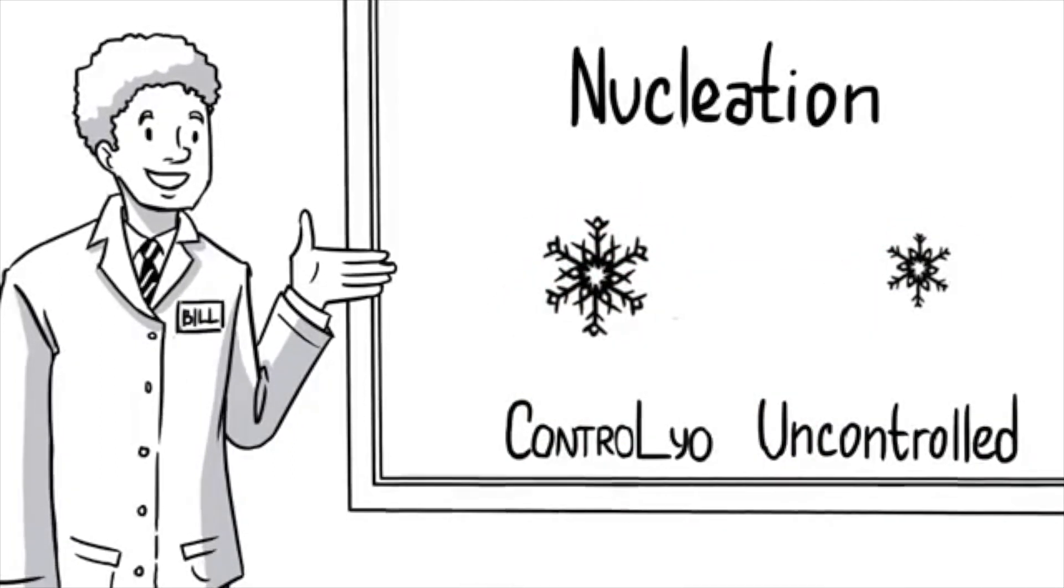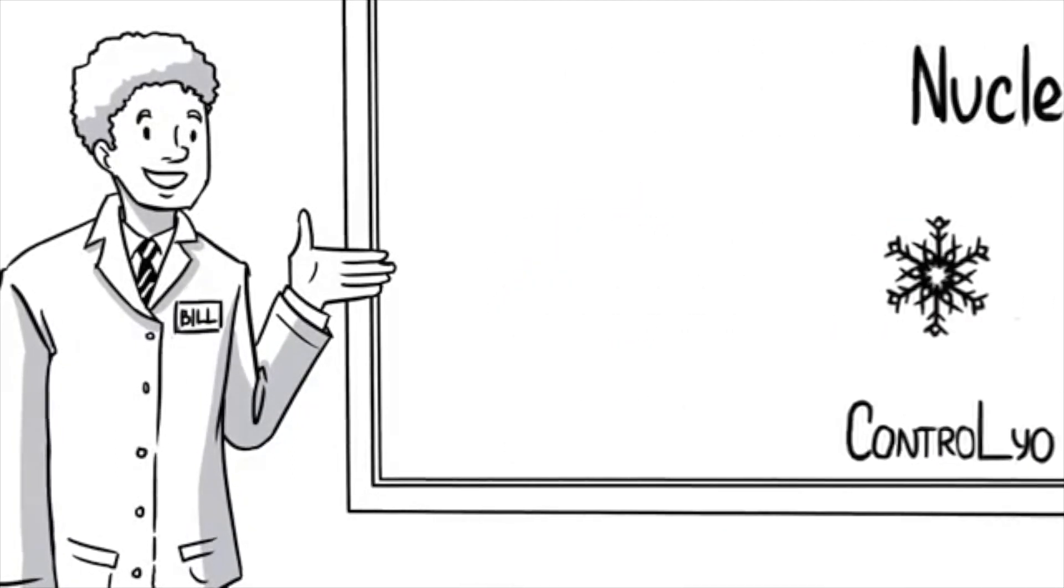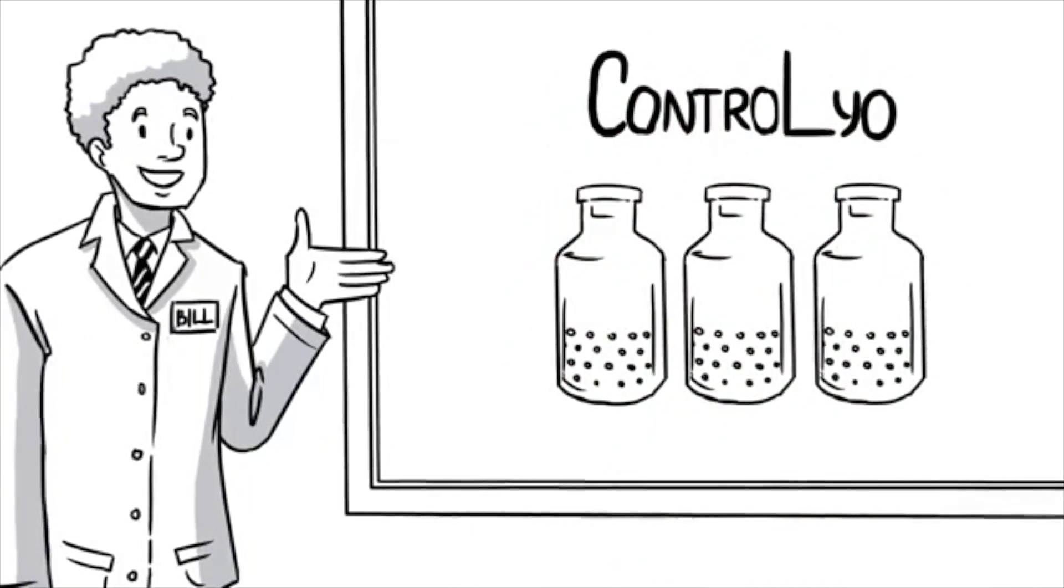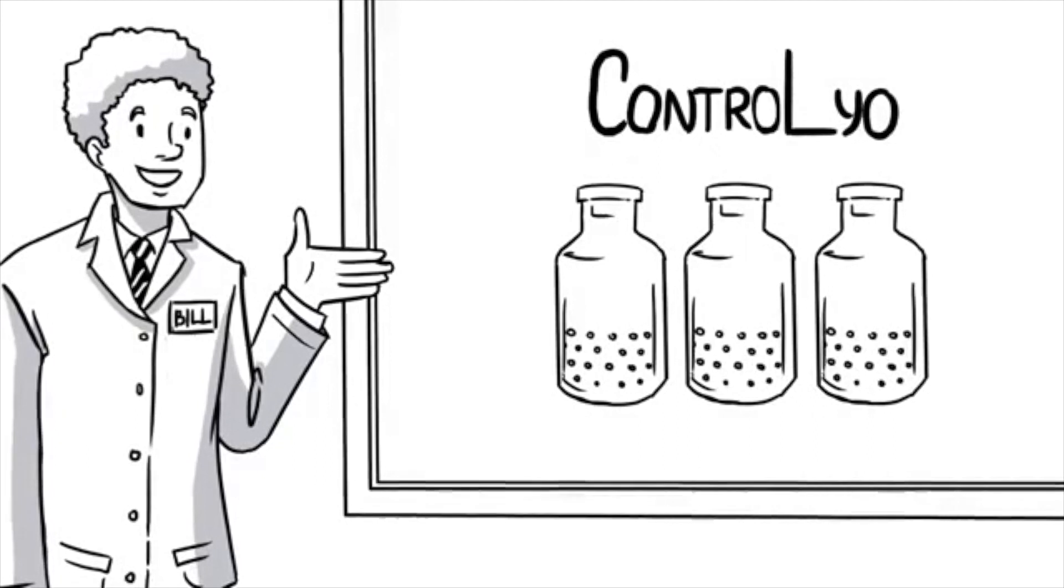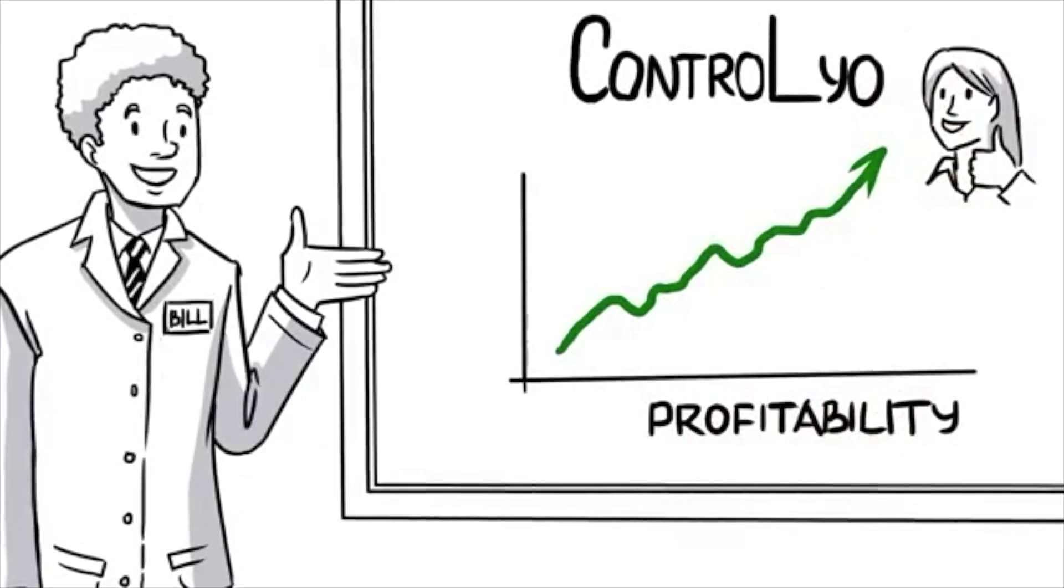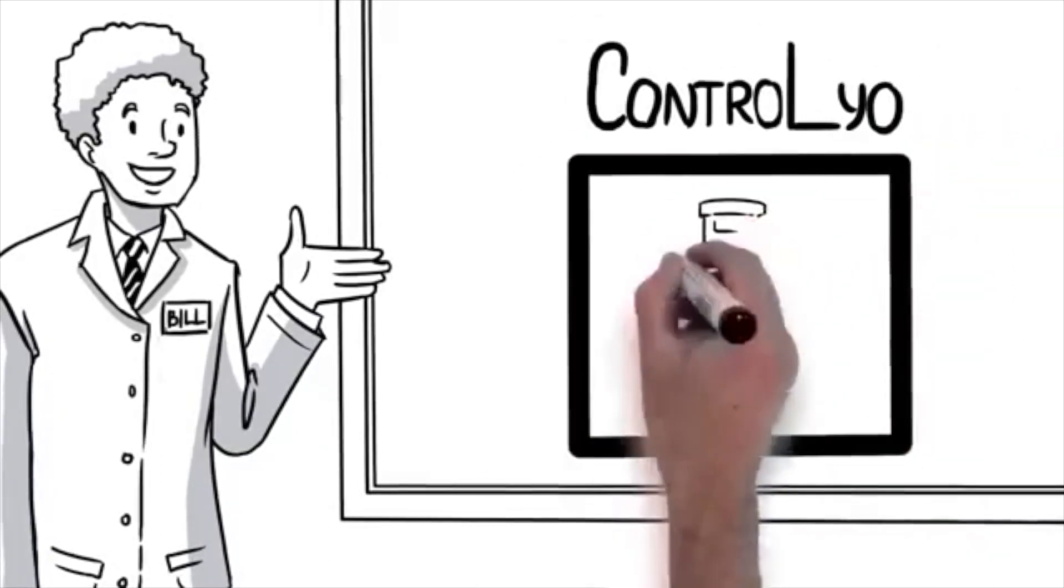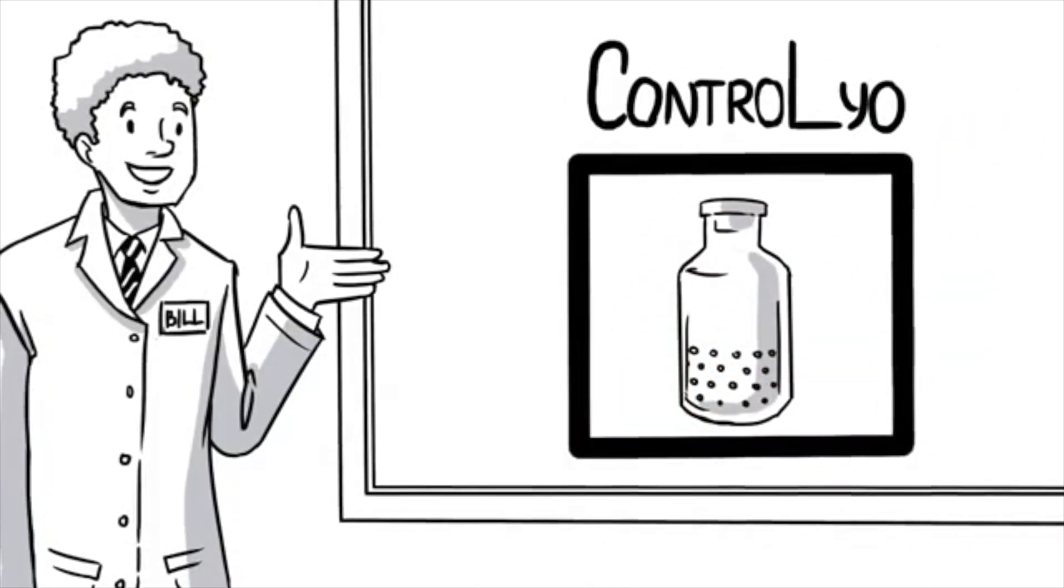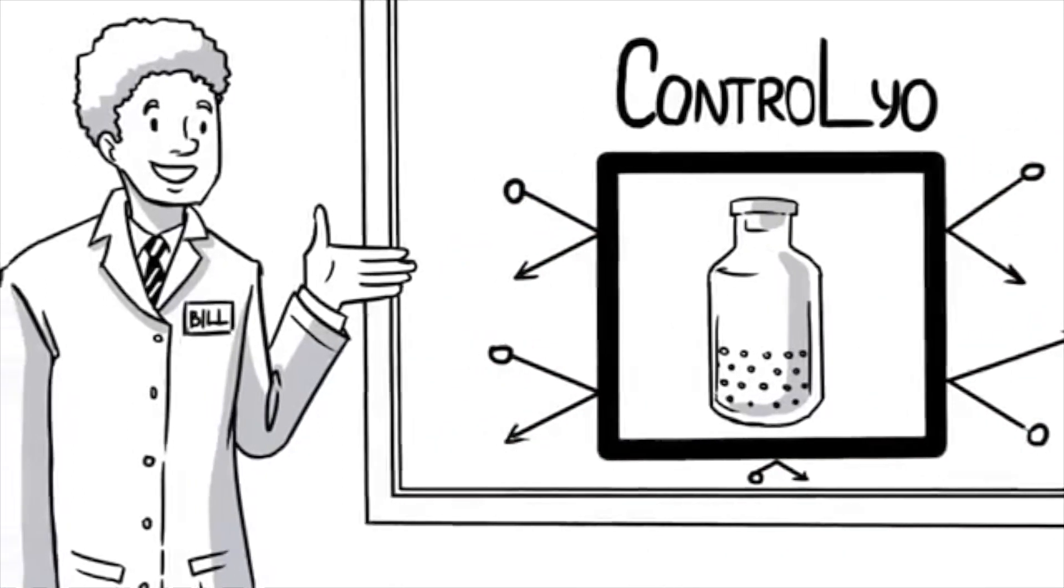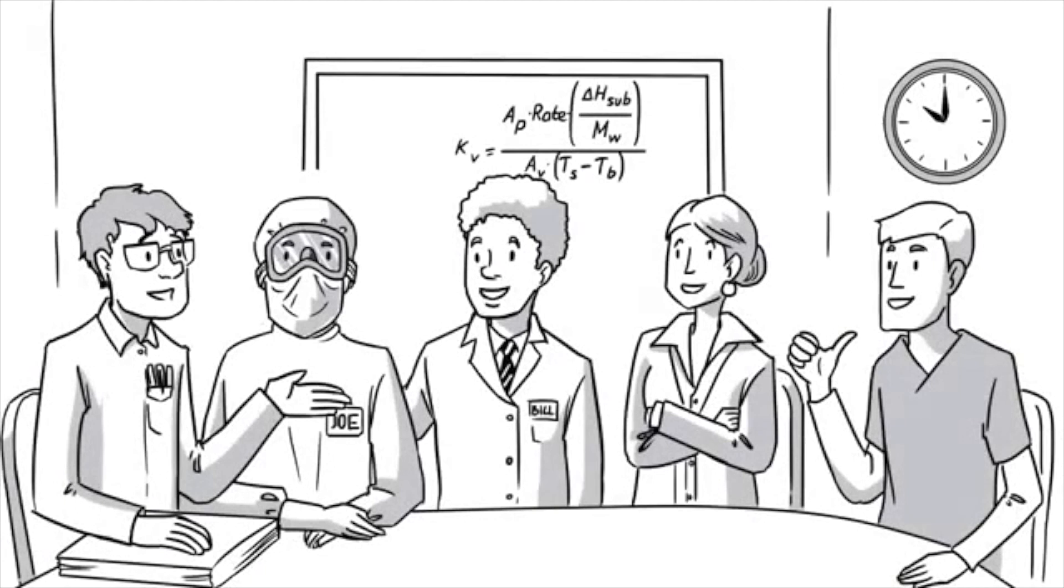These larger crystals allow faster sublimation due to less product resistance. Basically, having this control can mean shorter run times, reduced breakage, and improved batch homogeneity, which translates into increased profitability and happier customers. And it's all done while maintaining a sterile boundary. No foreign particles enter the chamber, so there's no risk of contamination.